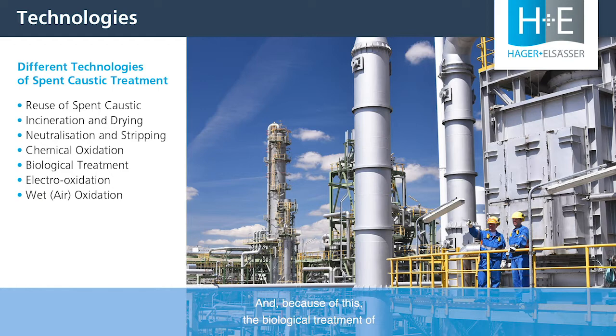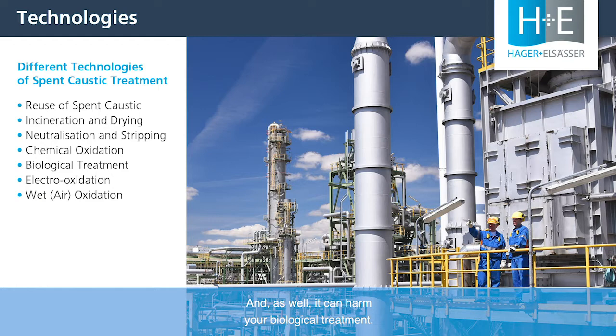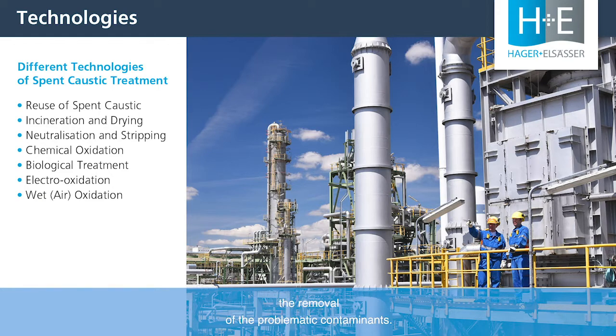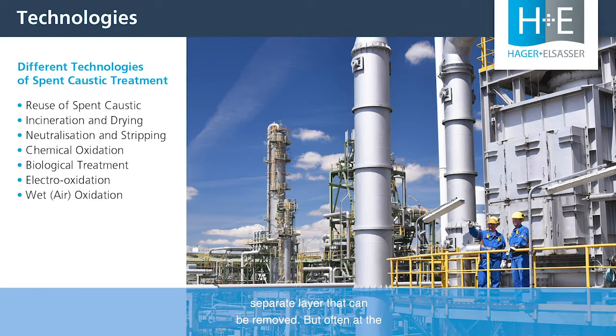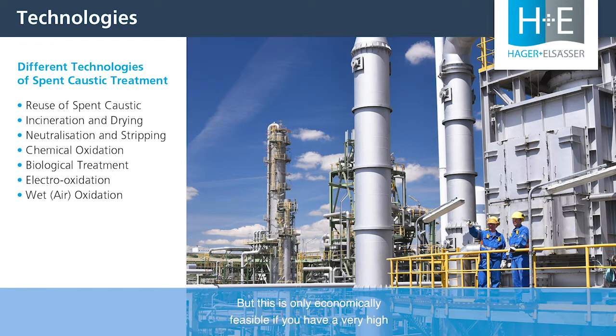The contaminants found in spent caustic are very often toxic, malodorous, and very hard to treat — you need very harsh conditions to achieve destruction of those contaminants. Because of this, biological treatment of spent caustic is often very problematic and can harm your biological treatment plant. There are other strategies to pre-treat spent caustic, such as removal of problematic contaminants: you neutralize the solution, then strip out the H₂S and remove organics that form a separate layer.